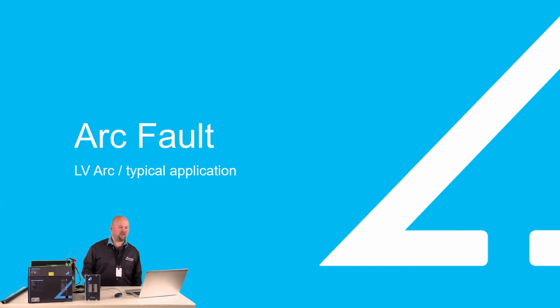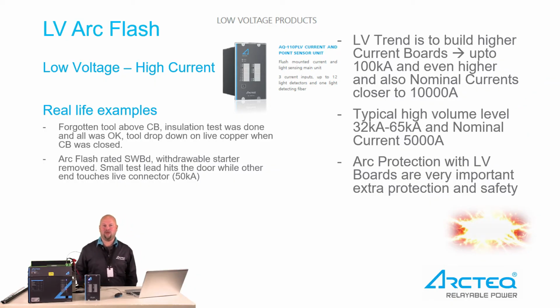So let's move on. Low voltage arc typical application. Low voltage, high current. Low voltage panels are very often underestimated. There can be an extremely high amount of current. If the arc can ignite, the current will hold and it will hold the arc flash as long as there is energy to feed the fault.